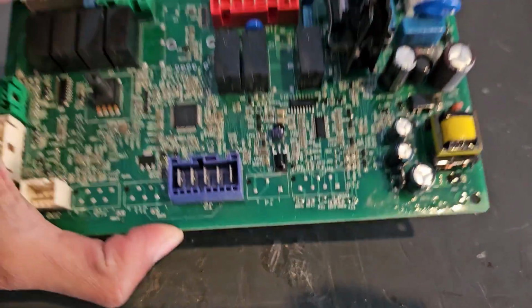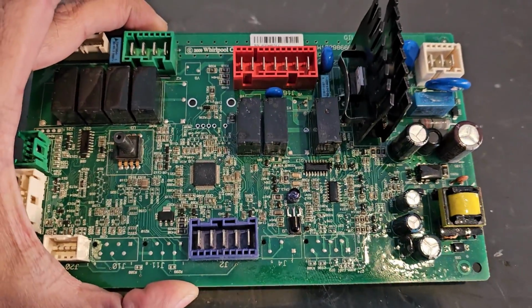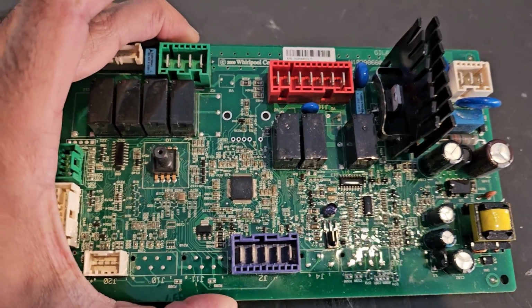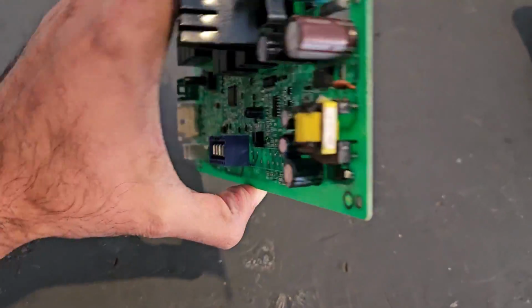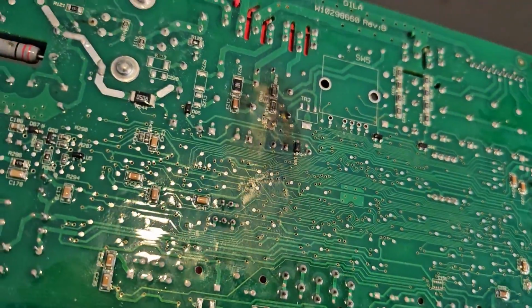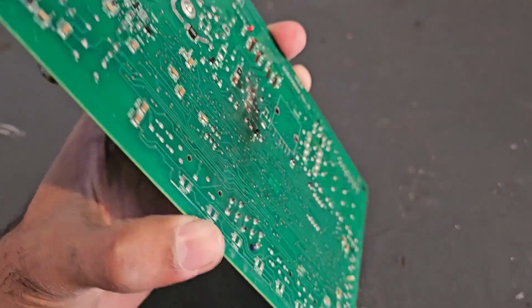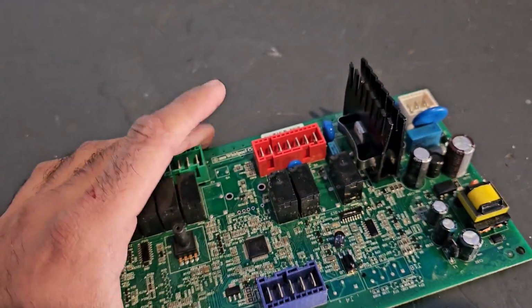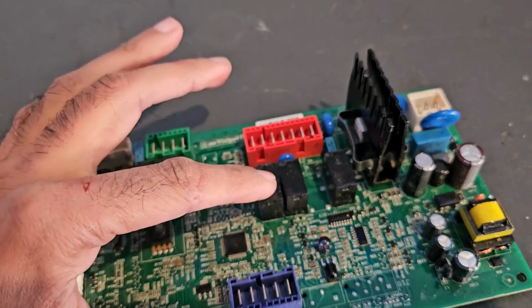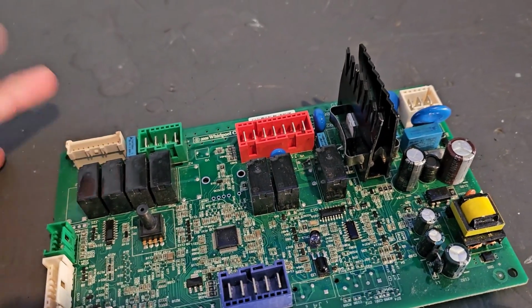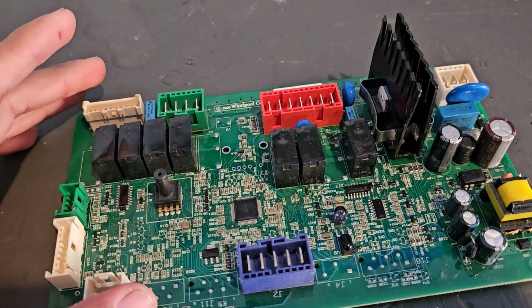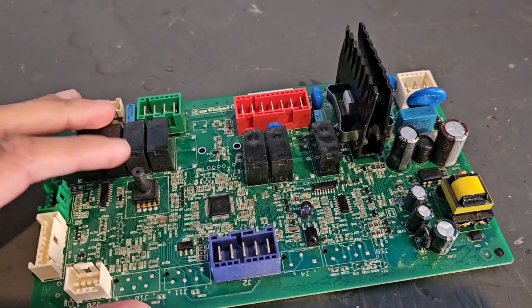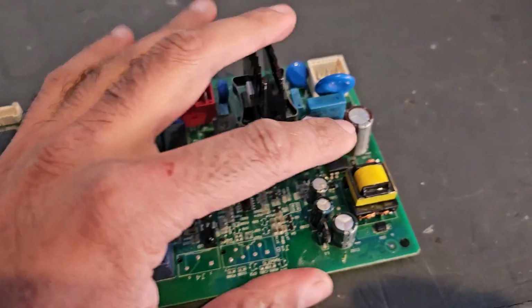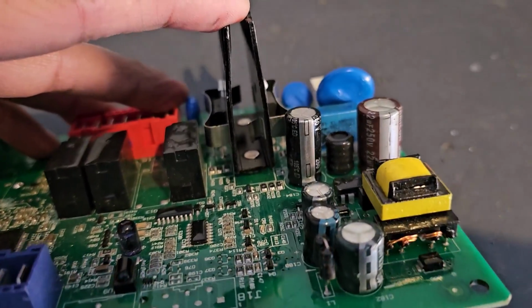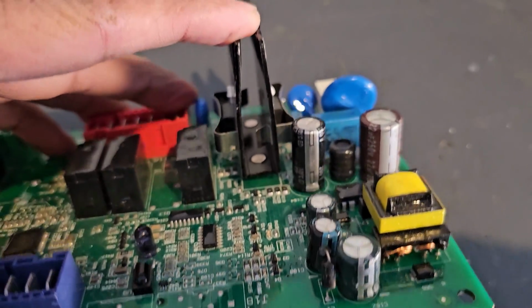So the very first thing I do when I pull out a control board is I examine it for defects. Now, sometimes they're apparent, like char marks or burn marks. Like, we can see that burn mark is right under some of these relays right here. So if I was just to replace these two relays or one of these relays, that's probably what was causing this issue. But then another physical thing I look for is to see if there's any sort of bulge on these capacitors. In this case, it's not.